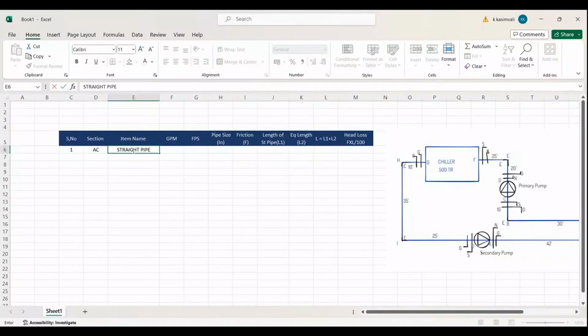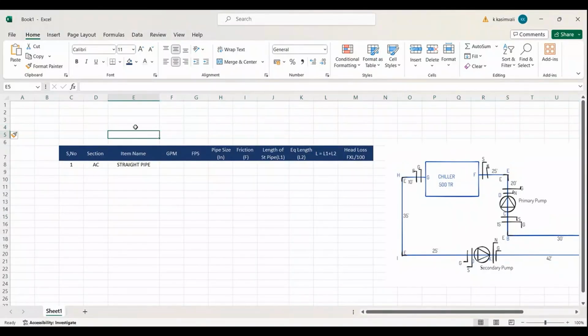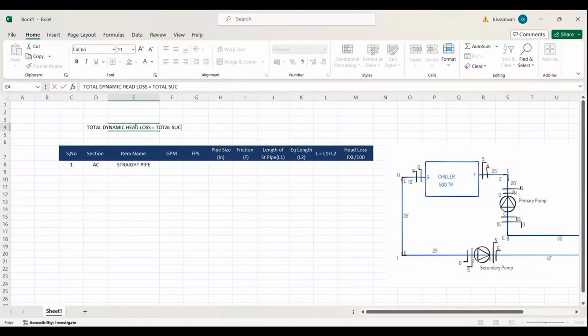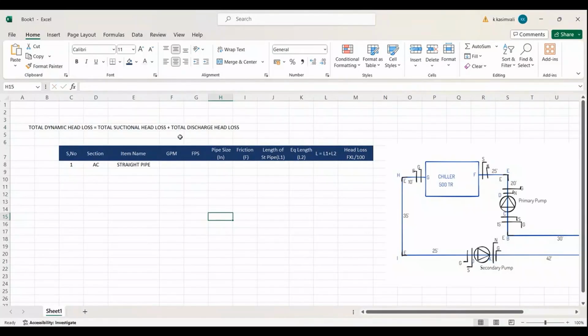So basically I'll explain here. To do the pump calculation, we need to have the total dynamic head loss. Total dynamic head loss calculations. Total dynamic head loss equals total suction head loss plus total discharge head loss. So while calculating total dynamic head loss, first we calculate total suction head loss.